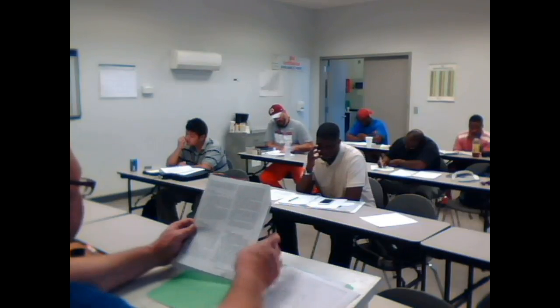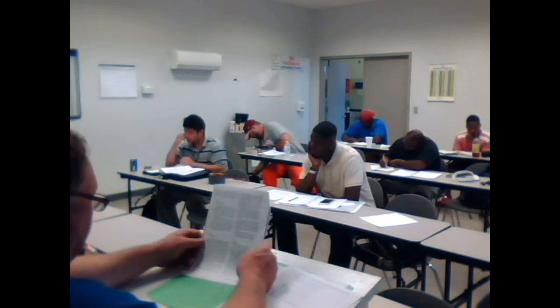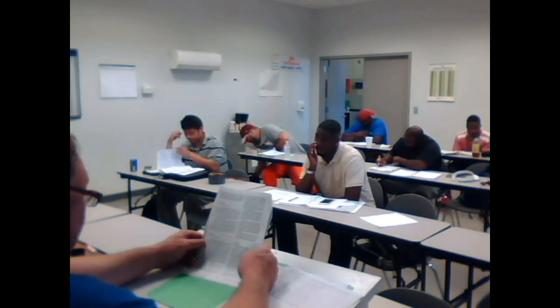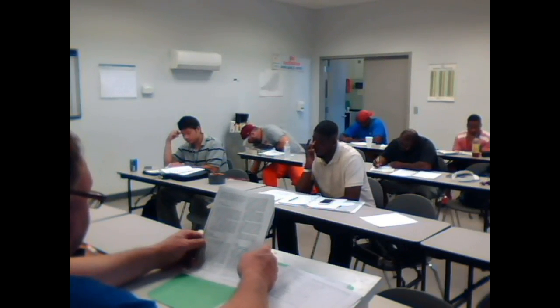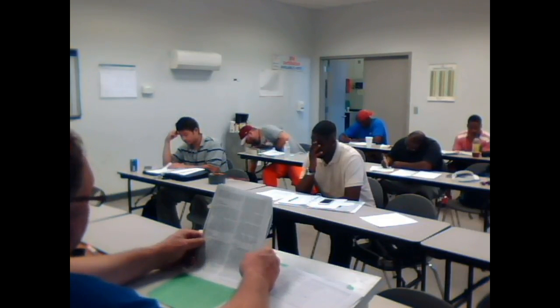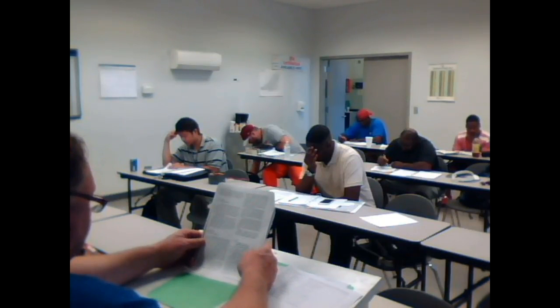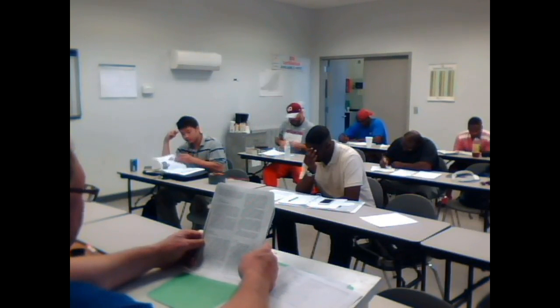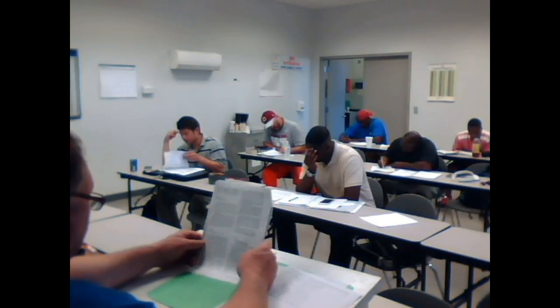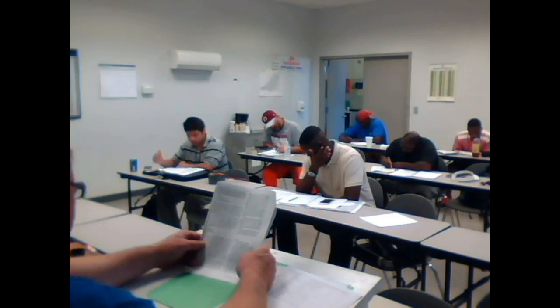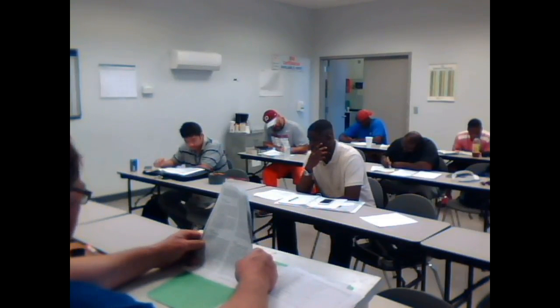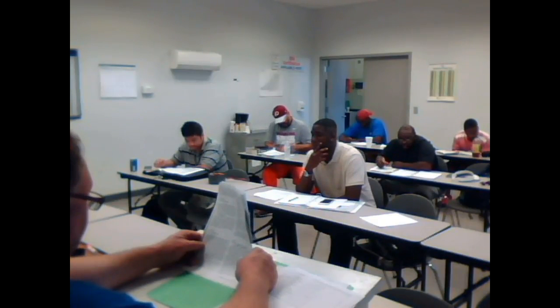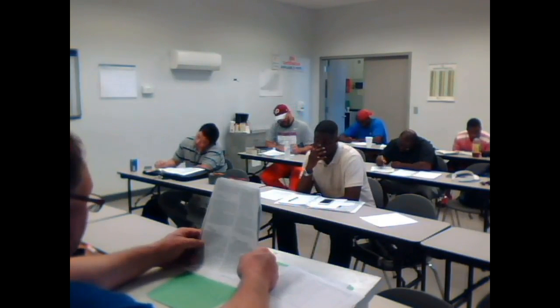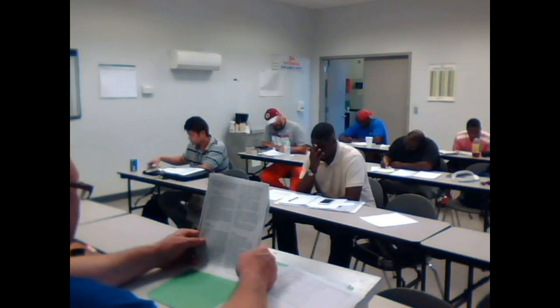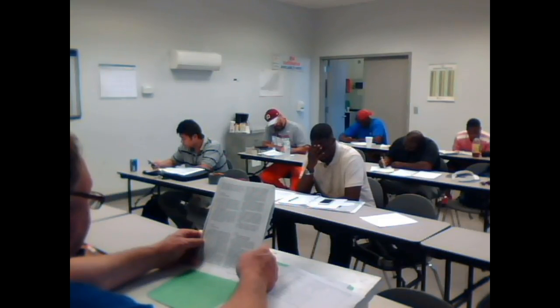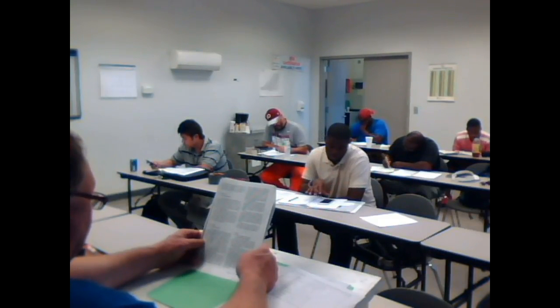All right, let's look at voltage load, section 2313. This sounds like a test question. Low voltage is the most common voltage problem, so chances are it's going to be low, not high. Single phase units are designed to start running at a minimum voltage of 10% below rating. On a 240 volt unit, that means 216. Anything below it, we don't even know if it's going to start. On a 3-phase unit, the minimum is 5%. That means that the minimum applied voltage for a 3-phase 208/230 volt unit would be 197.